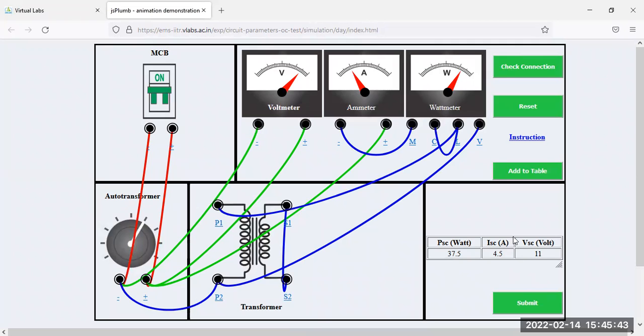So from this table, you can calculate the value of resistance and reactance referred to the high voltage side. So I think we already explained this a few minutes earlier. So your calculation can be completed just from this table. Okay. So you have power consumed during the short circuit test, that is 37.5 watt, 4.5 ampere current at 11 volt. So how can we find the resistance value? Just tell me.